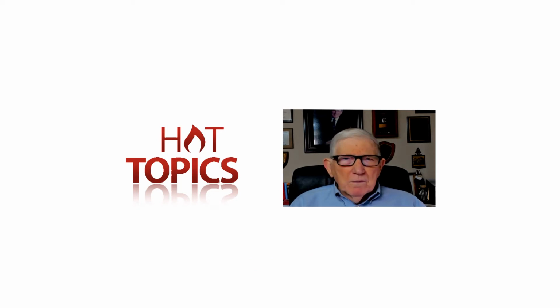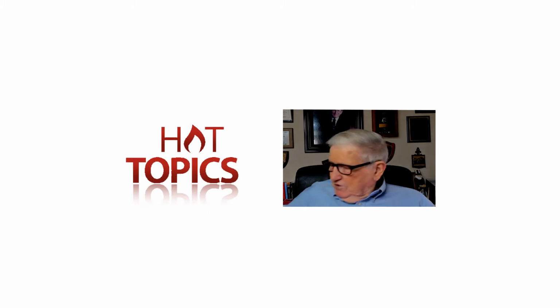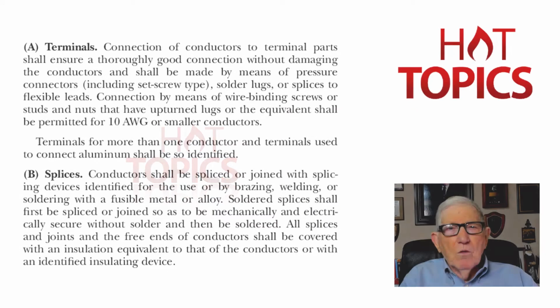Could we talk a little bit more about what I meant by 60-degree C terminals, 60/75-degree terminals, and 75-degree terminals, and exactly what would I go to in the code to pick this up, and just basically do a video on it. So that's what we're going to do, and we're going to be talking about 110.14 C as in car 1.